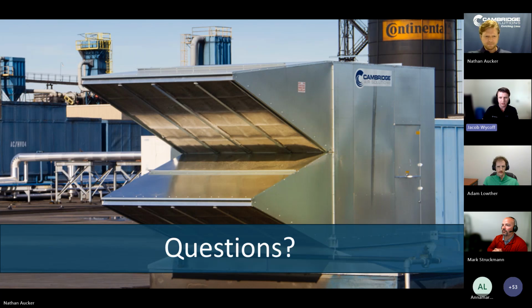You'll still have some noise from the fan, as that noise from the fan goes into the building, and the noise and vibration surrounding the ductwork. But if you use vibration isolation effectively on a pad-mounted unit, you're going to get very, very minimal vibration and noise entering the facility. Because that unit's going to be completely isolated from the building, you're not going to have the building up on the roof potentially shaking. There are ways to mitigate that on a roof-mounted unit, but putting it on pads is really the easiest way to do it in most cases.